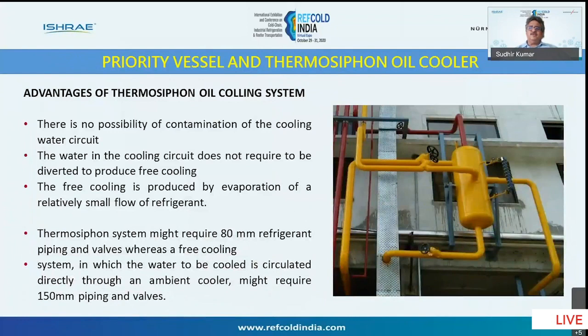Then comes the thermosiphon oil cooling, where the liquid from the receiver is used for cooling the oil. Normally we used to have water from the cooling tower to cool the oil, but that has two inbuilt disadvantages. One is if your water quality is bad, you will damage your oil cooler and the oil cooler tubes will leak. The other disadvantage is you are using a pump of maybe 5 HP for one oil cooler. And if you have 5-6 oil coolers, you will be consuming a lot of power for pumping water into the oil coolers.